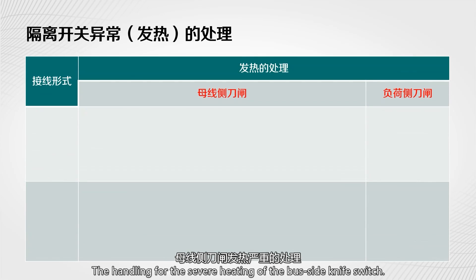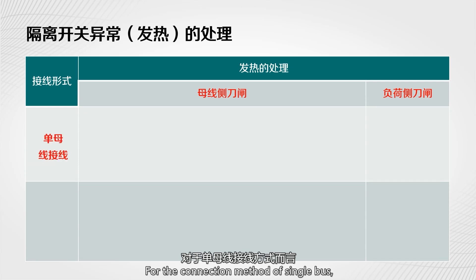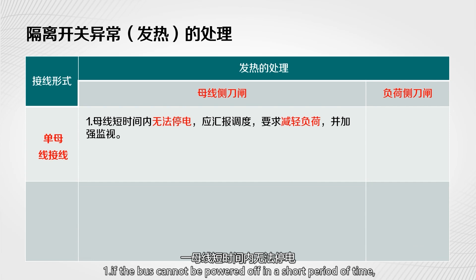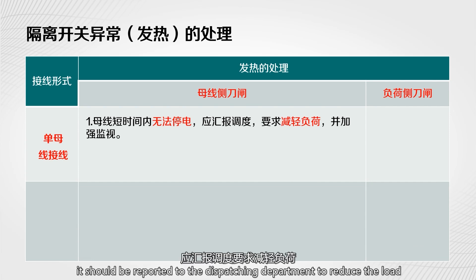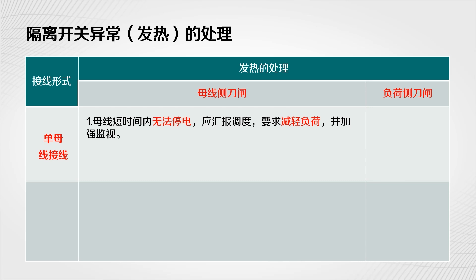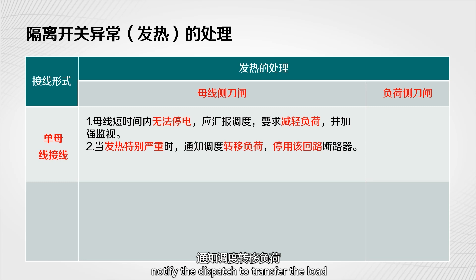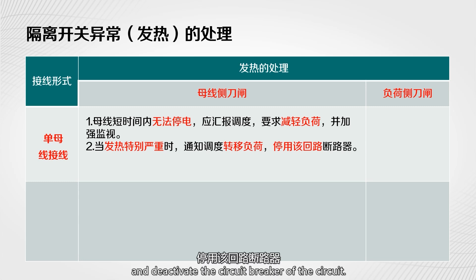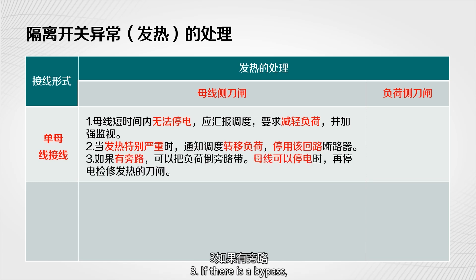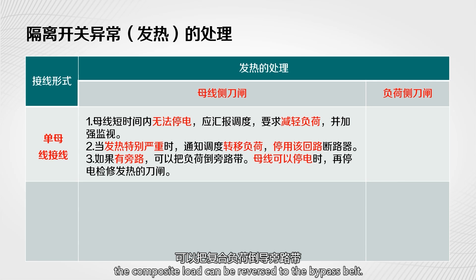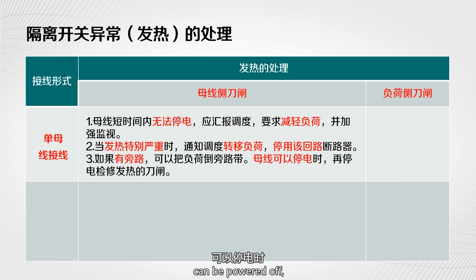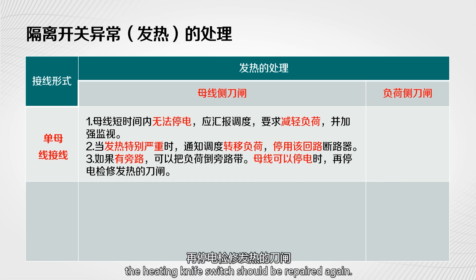Handling for severe heating of the bus side knife switch — single bus connection method. First, if the bus cannot be powered off in a short period of time, report to the dispatching department to reduce the load and strengthen monitoring. Second, when the heating is particularly severe, notify dispatch to transfer the load and deactivate the circuit breaker. Third, if there is a bypass, the composite load can be reversed to the bypass belt. When the bus can be powered off, the heating knife switch should be repaired.